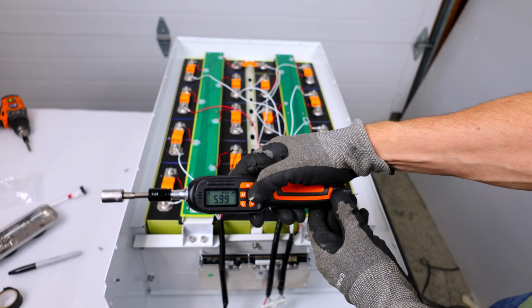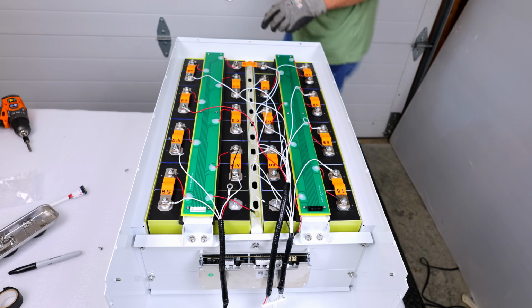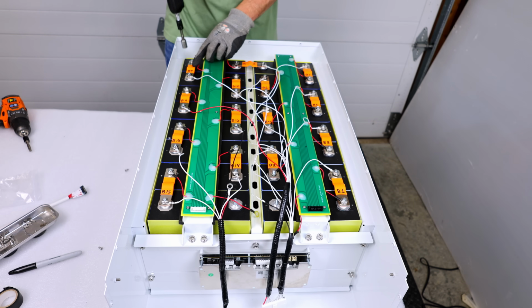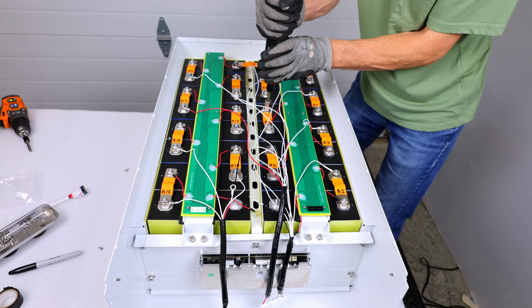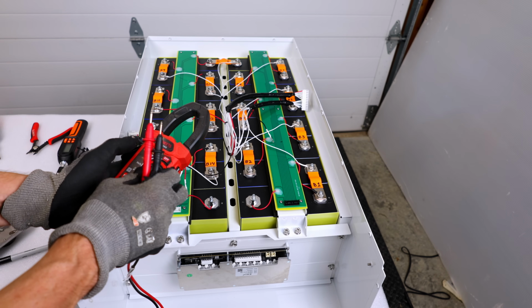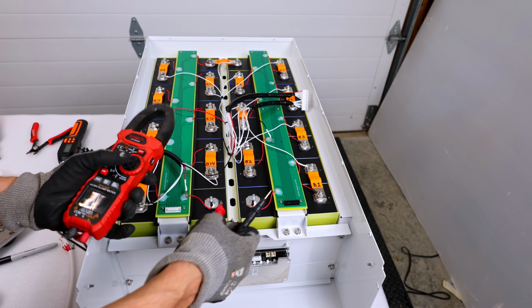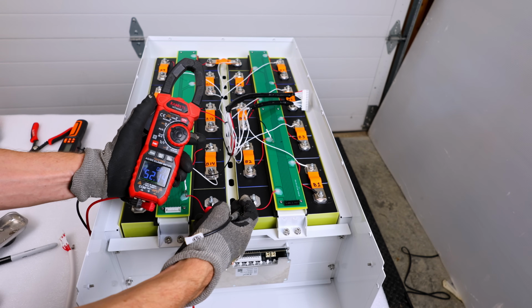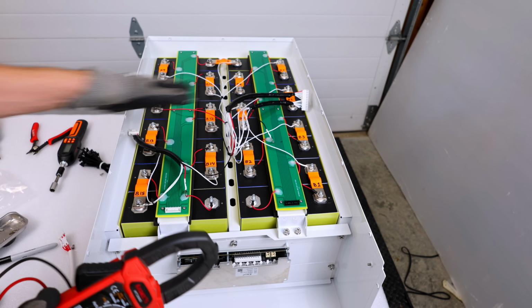Now I'll set my torque wrench to 6 Newton meters. There we go. I'll go ahead and torque these down row by row, making sure there's no insulation under them. Now before I go any further, let me just check the pack voltage. Should be a little over 52 volts, 52.15. That's a good indication that we've connected it properly.